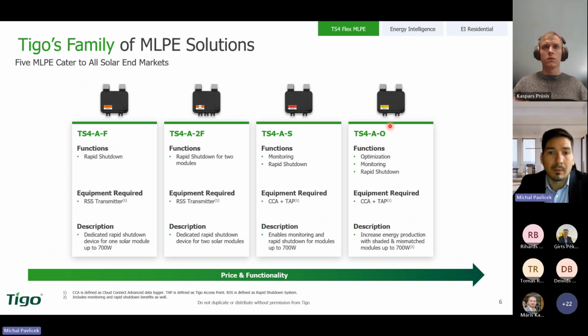In case someone thinks that they need just the safety, because maybe the budget is so short that the investor doesn't have enough money, or maybe the bank doesn't want to allow a slight increase of the budget, for those we may offer, for instance, the TS4-A-2F, which is the most competitive solution and has only the safety functions for rapid shutdown control, for the safe voltage at the PV level. The 2F means that it's for two modules. So this is the most cost-effective solution. In the middle, we also have the Model F, which is for a single module, or Model S, which combines rapid shutdown control and monitoring, but the optimization is not there. So, three products.